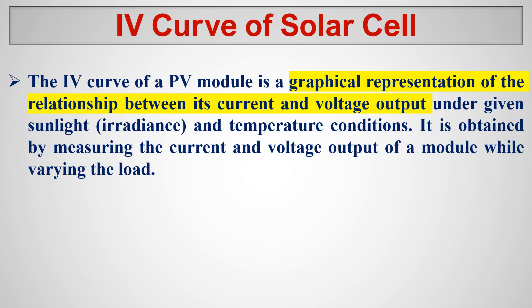The IV curve is a graphical representation of the relationship between the current and voltage output under given sunlight and temperature conditions. It is obtained by measuring the current and voltage output of a module while varying the load. By changing the load, we get different current and voltage outputs, and if we draw the graph of those different values, we get the IV curve.